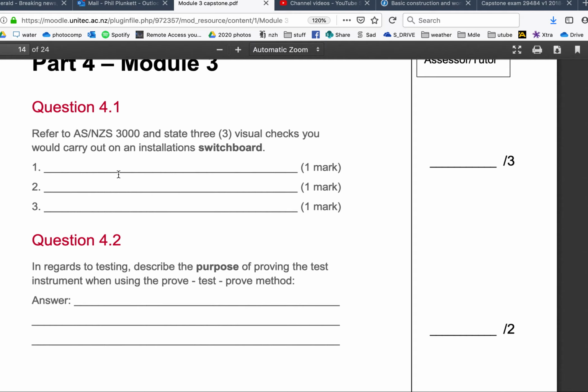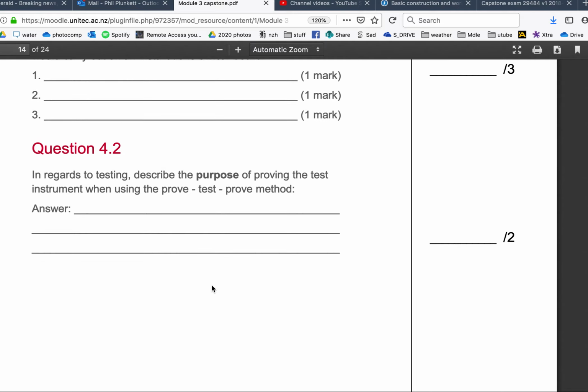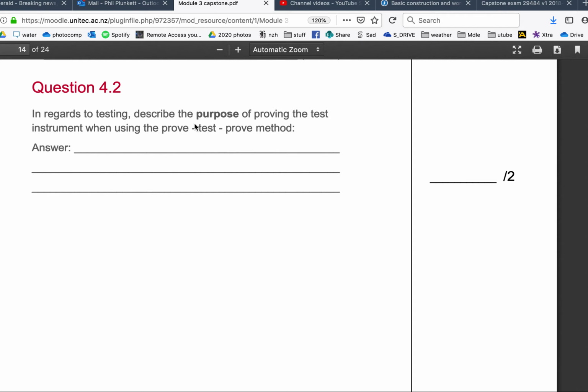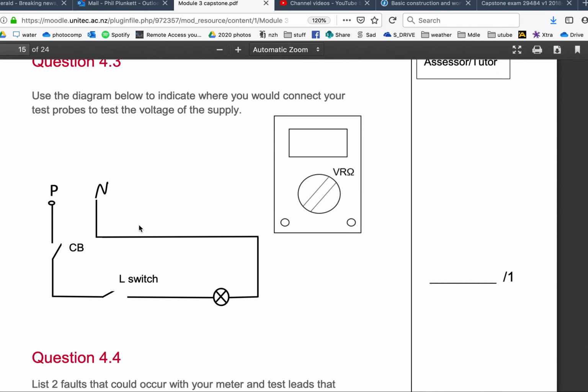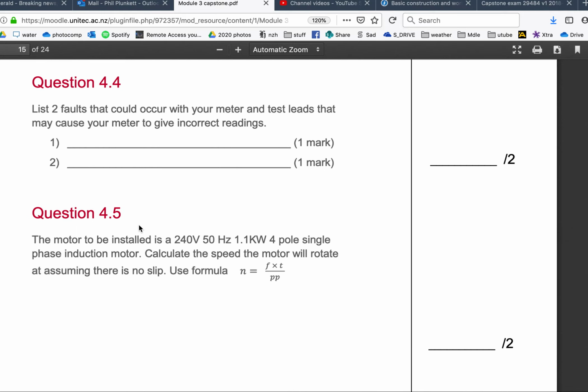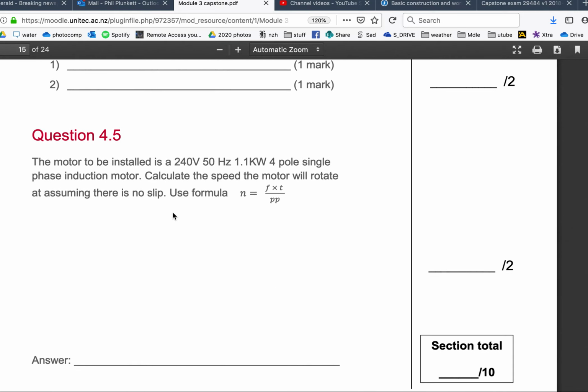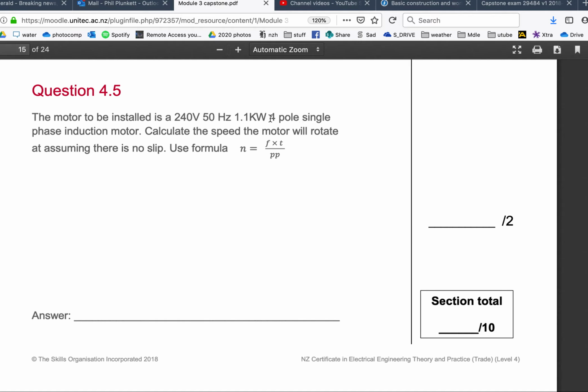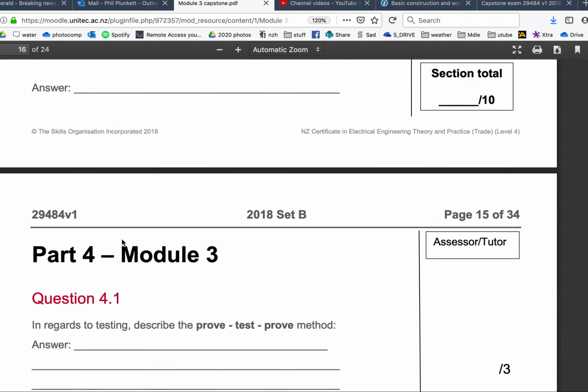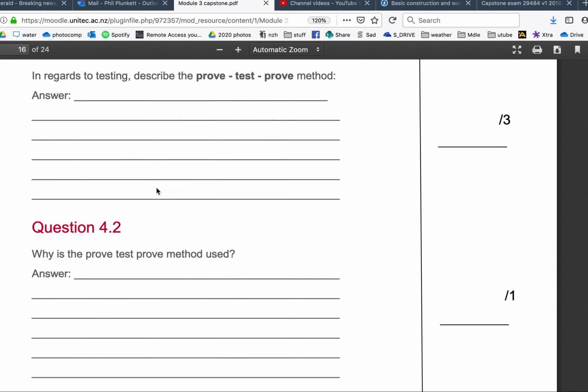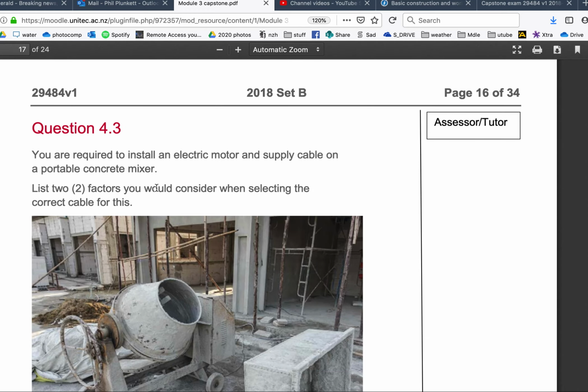Visual checks carried out on a switchboard. You're going to have to look that up. In regards to testing, describe the purpose of prove, test, prove. We just did that. Connect your, done that one, eh? 2 faults, lots of faults. Here's another one, 4 pole, 50 times 60, 3,000. 4 pole would be 2, so that'd be 1,500. Prove, test, prove.